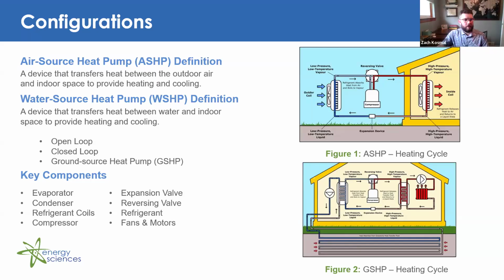So with water source heat pumps, you can have two different types of loops. So you can have an open loop system or a closed loop system. In an open loop system, the pressure in the system varies depending on the depth of the water source and the flow rate required to pump that water. So the system must overcome that static lift to draw that water from a well or groundwater or pond. And that may increase the pump energy demand. So to summarize, an open loop system must manage fluctuating pressures from water extraction and discharge, whether that be from a pond, well, or groundwater source. In a closed loop system, you have a constant pressure within that system, which is maintained within a sealed circuit of pipes.